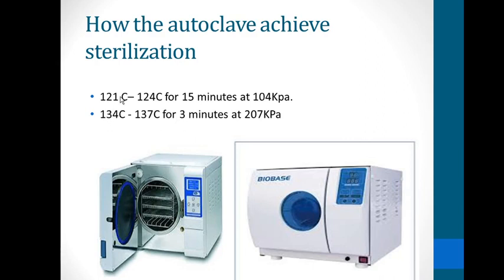If we raise the temperature to 134 to 137 degrees Celsius, the instruments will be kept in the autoclave for only three minutes. So as we raise the temperature, we reduce the time; when we reduce the temperature, we increase the time. This is inversely proportional.